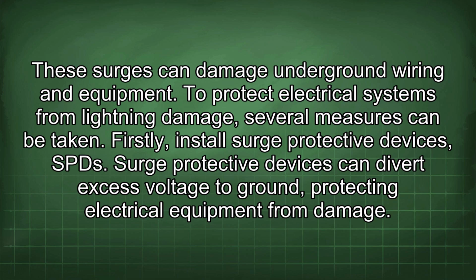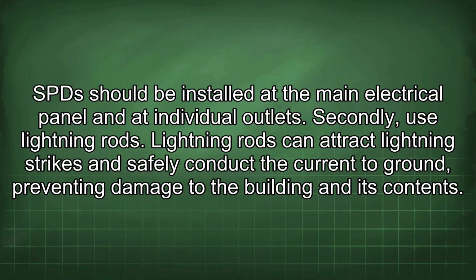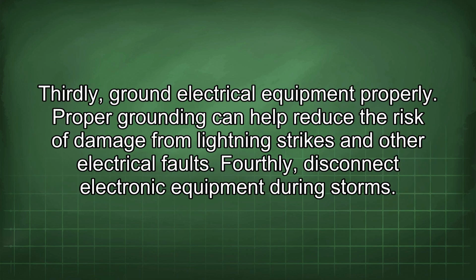Firstly, install surge protective devices, SPDs. Surge protective devices can divert excess voltage to ground, protecting electrical equipment from damage. SPDs should be installed at the main electrical panel and at individual outlets. Secondly, use lightning rods. Lightning rods can attract lightning strikes and safely conduct the current to ground, preventing damage to the building and its contents. Thirdly, ground electrical equipment properly. Proper grounding can help reduce the risk of damage from lightning strikes and other electrical faults.